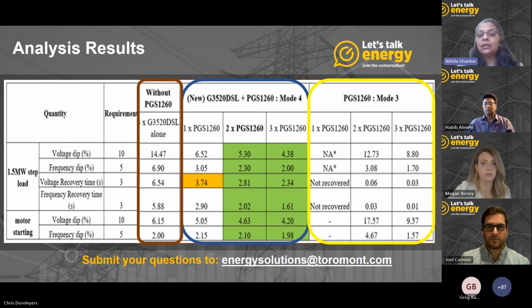We didn't get a satisfactory result when it comes to the voltage dip. As you can see, it's higher than the 10% specified. However, 3 units of 1260 kilowatt battery energy storage did meet all of the requirements. But the main point to be noted here is that the energy output from the batteries is for a limited period of time. So the best solution, of course, is the combination of the generator set and the battery energy storage system.